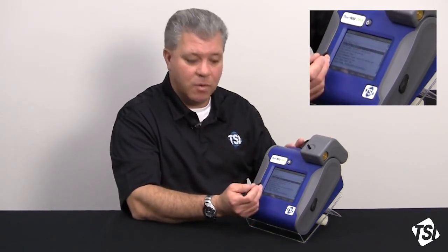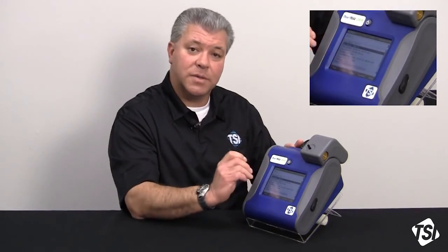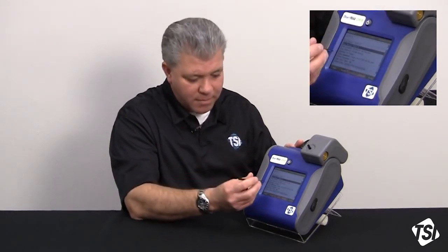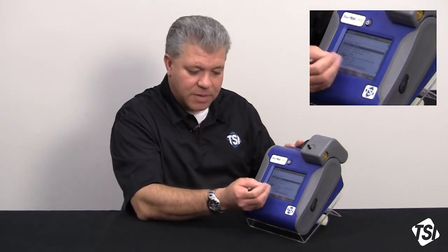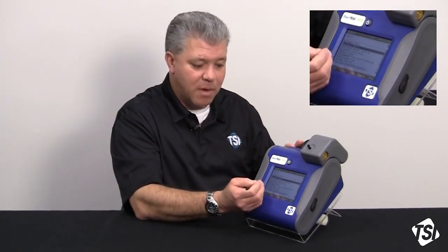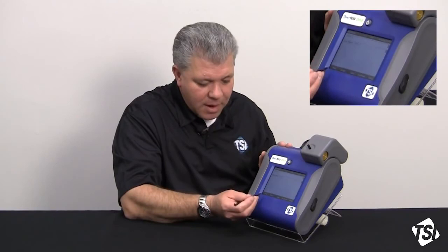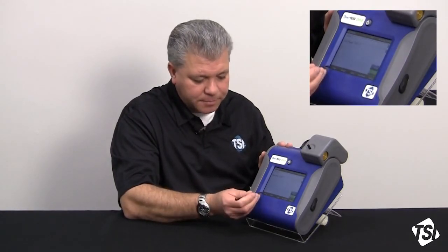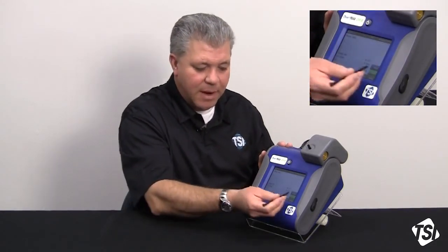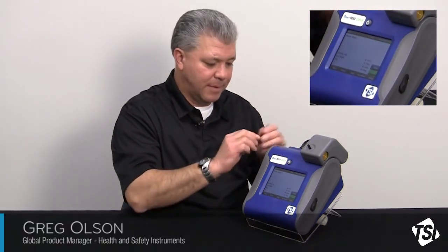Now I can go back through the rest of the program log mode and set up my test length. I can reset, if I need to, my log interval, but again, that's no less than 2 minutes. It could be 2 minutes, it could be as great as 1 hour. I can set all my other parameters. How many samples do I want to take? Do I want it to be a continuous run? So on and so forth. Once I get all of this programmed, I simply hit main, go back to the main screen, and I'm ready to start sampling.